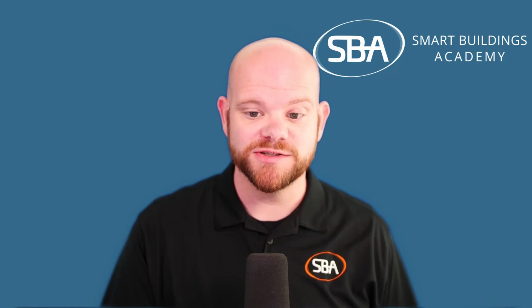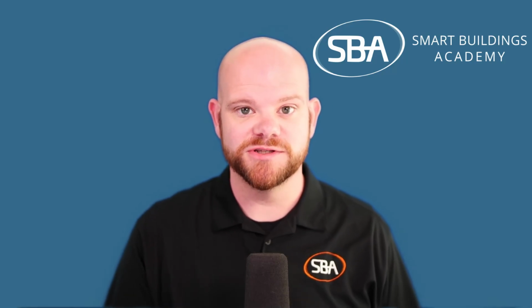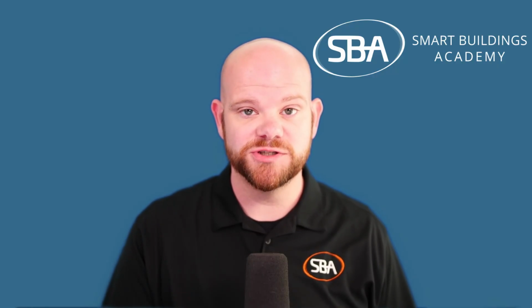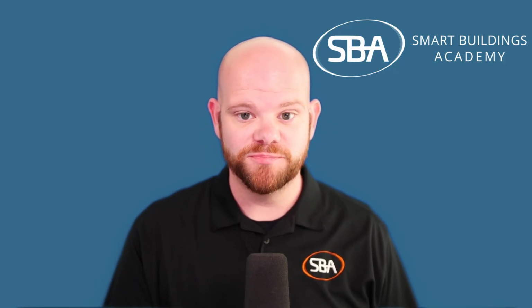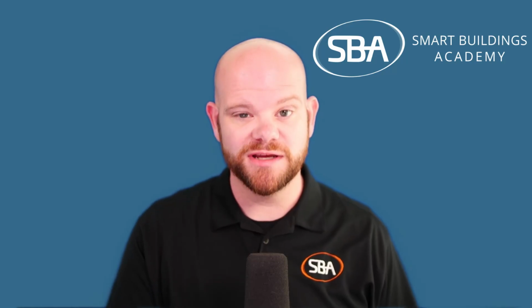So let's start off today's episode by understanding what commissioning is. Commissioning, simply put, is the structured QA process of our BAS system. What this does is allow us to verify all the components of the BAS system, and make sure that they're operating how they're supposed to. It verifies the actual performance compared to the design intent from the engineer or the sequence of operations. This commonly includes documentation and testing as well. And the big important thing to remember here, guys, is that commissioning is not simply turning things on and off, okay? Remember, we're checking devices, we're checking points, we're checking logic, all these things. We're checking everything with our system when we do the commissioning, okay?